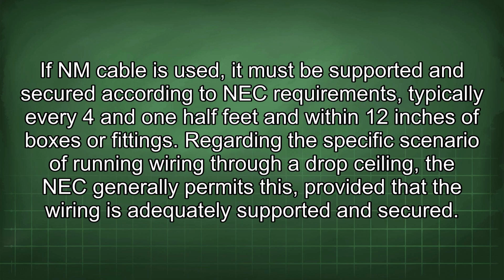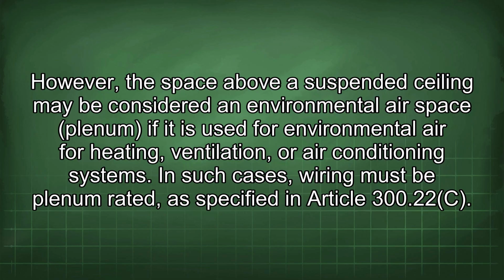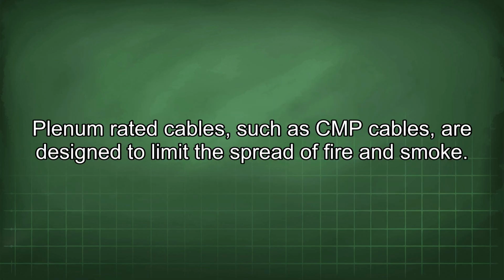Regarding the specific scenario of running wiring through a drop ceiling, the NEC generally permits this, provided that the wiring is adequately supported and secured. However, the space above a suspended ceiling may be considered an environmental air space plenum if it is used for environmental air for heating, ventilation, or air conditioning systems. In such cases, wiring must be plenum rated, as specified in Article 300.22(C). Plenum rated cables, such as CMP cables, are designed to limit the spread of fire and smoke.